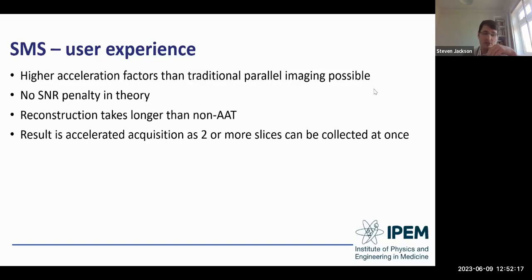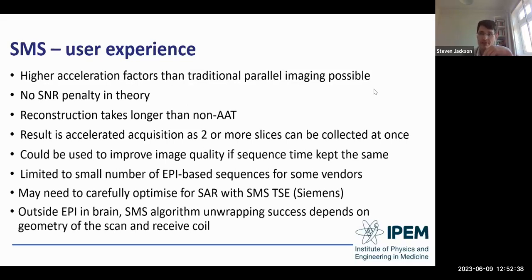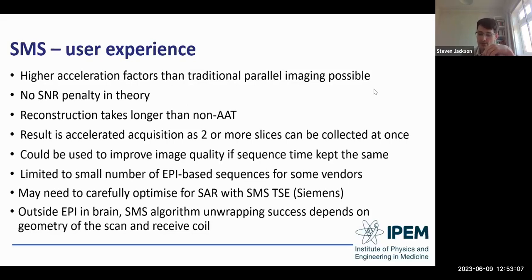From user experience with SMS: higher acceleration factors than traditional parallel imaging are possible with no SNR penalty in theory, and in practice where adequate receive coil coverage exists. The result is an accelerated acquisition as two or more slices are collected at once. It's currently limited to a small number of EPI-based sequences for some vendors. With the Siemens implementation, because novel RF pulses are exciting two or more slices at once, SAR needs to be carefully optimized. Outside EPI brain imaging, the SMS unwrapping algorithm success can depend on scan geometry and receive coil, so each implementation needs testing to ensure adequate image quality.